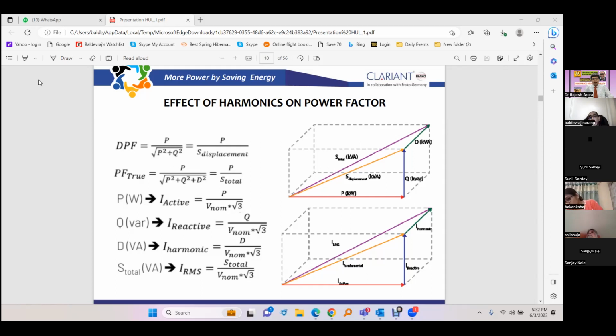And STATCOM, if it is available, it will solve the problem. So what we have seen, and we have tried to find out from other overseas countries also what they have been doing and what the situation was there, is that whenever there is an issue like that, whenever there is a fault condition, the STATCOMs go out of service within maybe a quarter of a cycle, because their firing angle changes and they go out of service. So they are not available to support this reactive power requirement for which they are being promoted. That is one of the major reasons. So when they are not available, why go for that? Even if we put them in, where is the solution going to come from if they are not available?